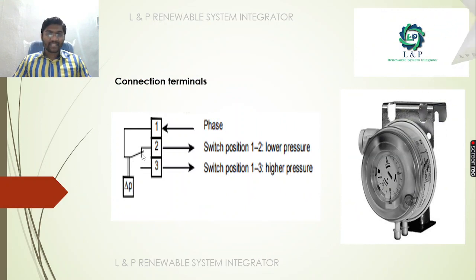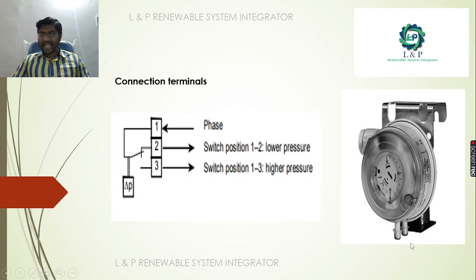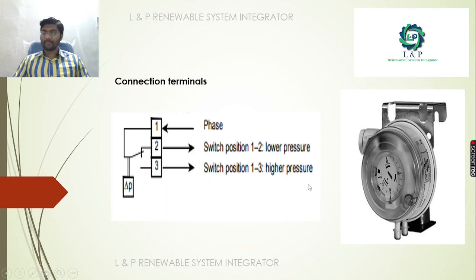The connecting terminals — terminals 1 and 2 — are normally the closed portion, which is always used for low pressure. In most cases, we monitor the high pressure points. When high pressure occurs and it is greater than the set point, the contact changes from 1-2 to 1-3, giving continuity.